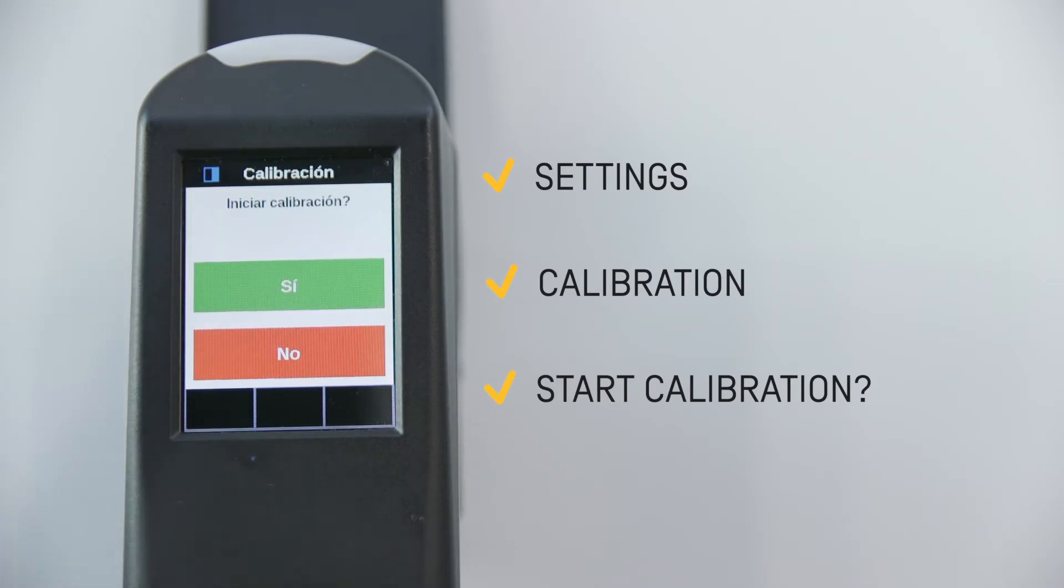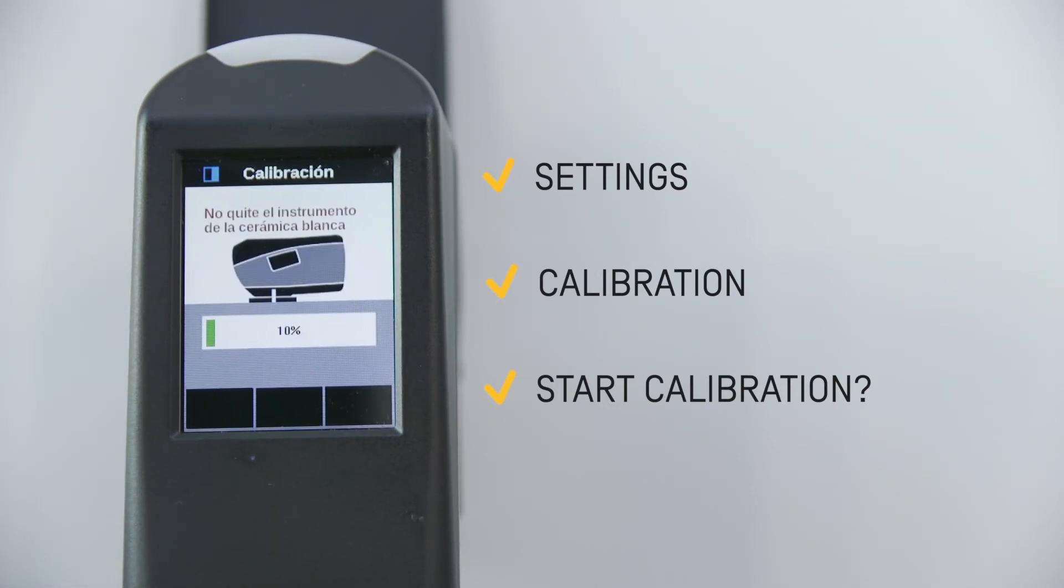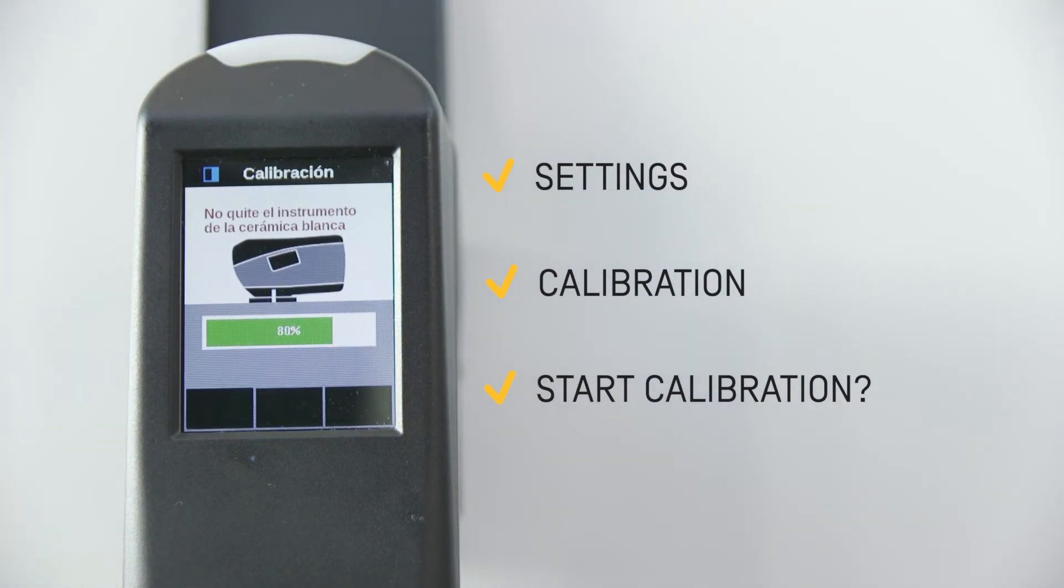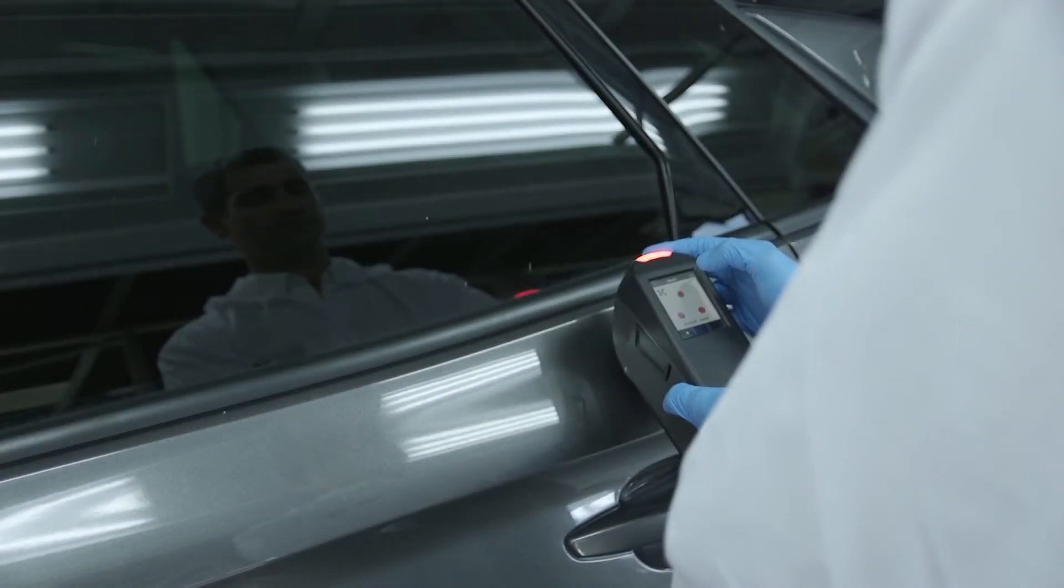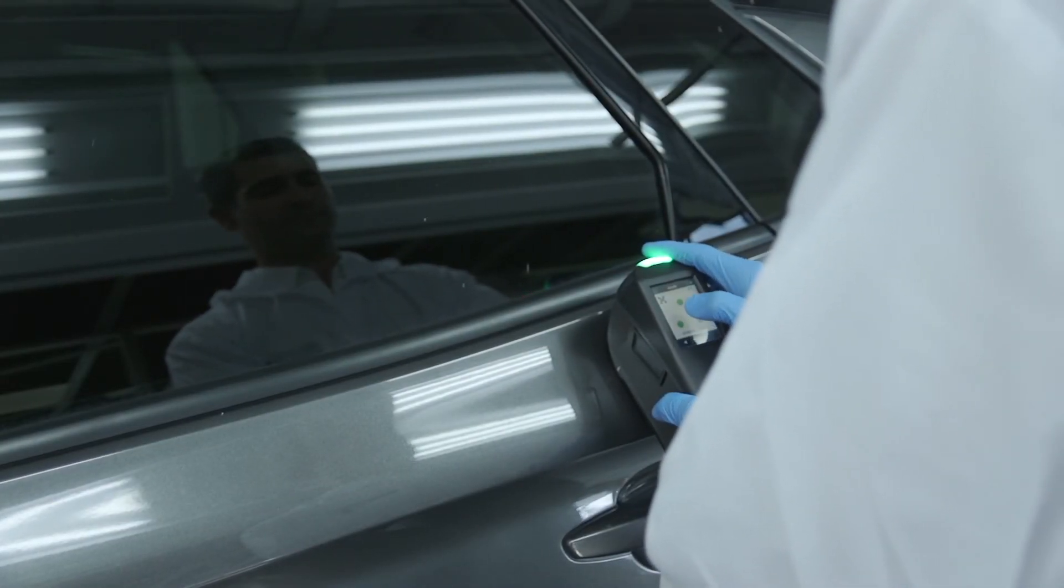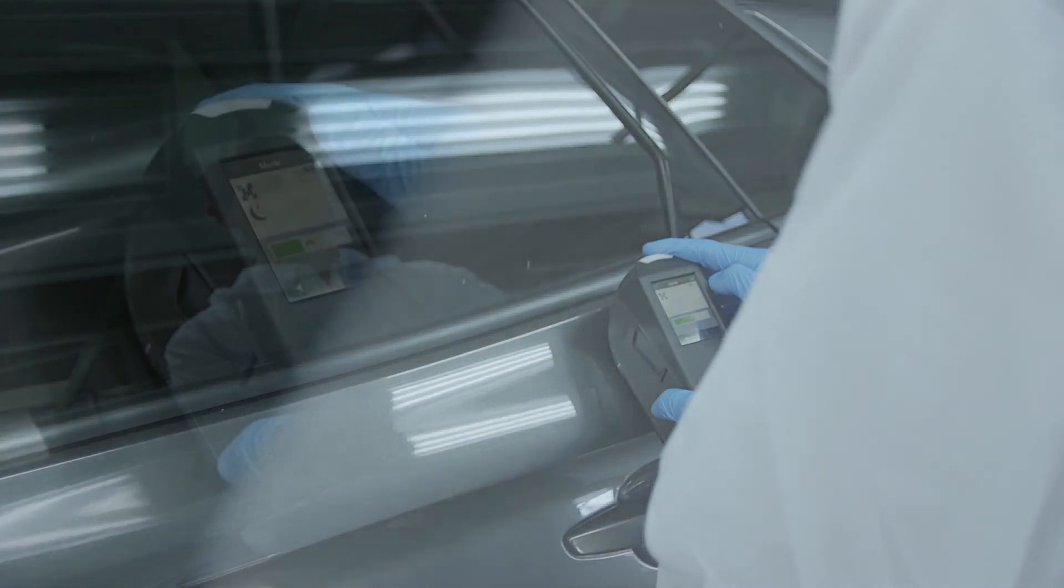Do not remove the spectrometer from the white ceramic plate until the calibration process has been completed. Finally, a notification will appear on the screen confirming that the calibration has been completed. The spectrophotometer will then be prepared to perform measurements on the vehicle's surface.